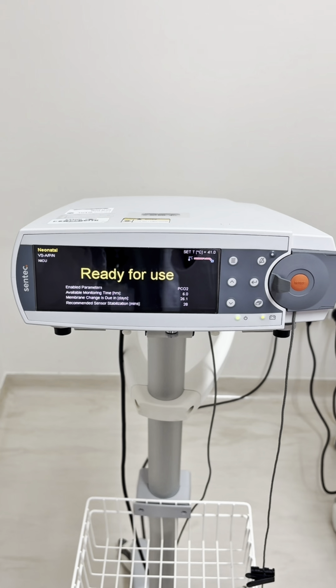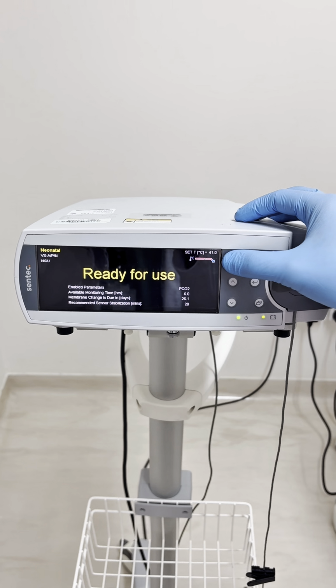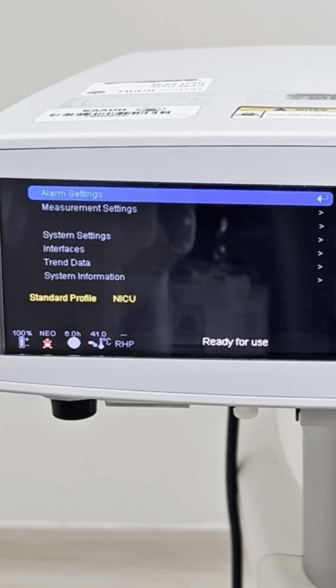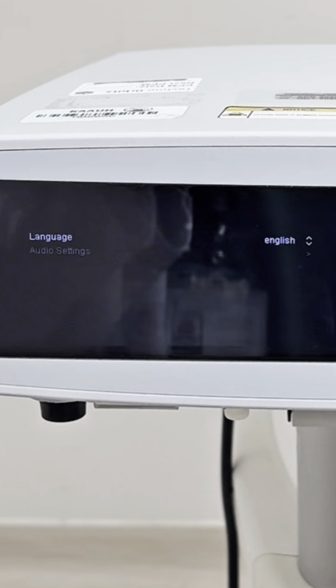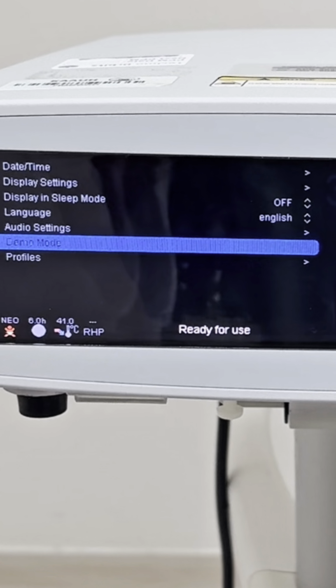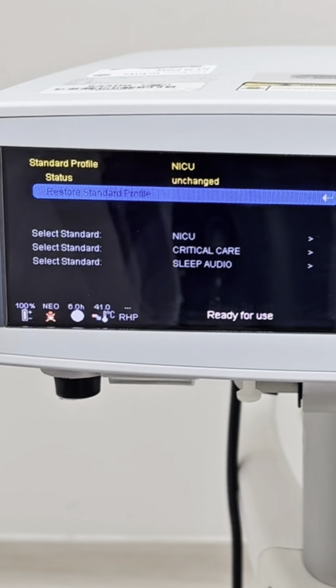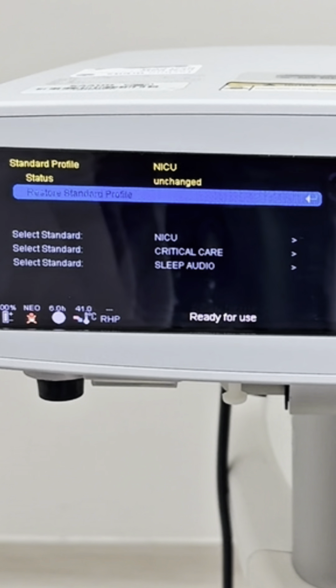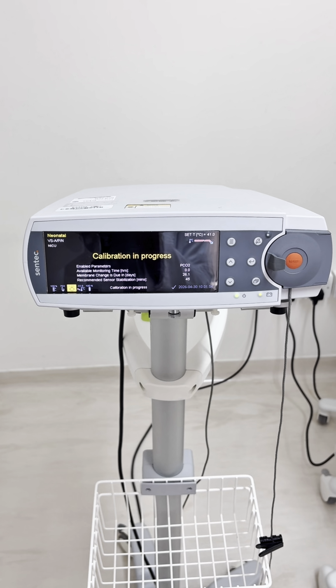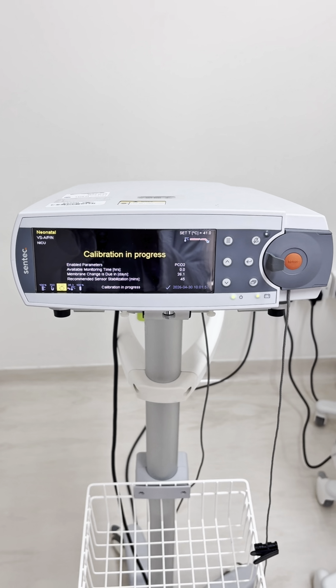To choose the patient category, press on main menu. Go to System Settings. Then go to Profile. The device will show you 3 profiles. First, NICU, used for neonates and pediatric up to 40 kilos. Second, critical care, used for adult. Third, sleep audio, used for sleep study. The device will perform another automatic calibration after selecting a profile.